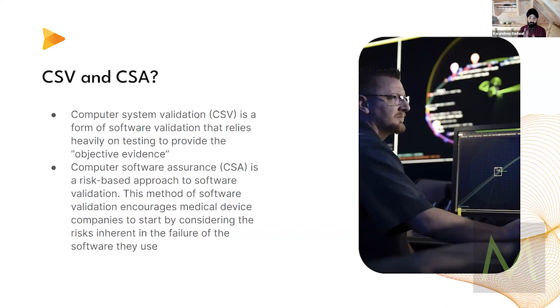I know the FDA is moving towards CSA, but for the purpose of today I'm going to be focusing on CSV. When it comes to CSA, there's a conversation we can have another time. The trick is kind of like the wording used in ISO 14971 and ISO 13485 — we take a risk-based approach. The higher risk things, yes, we need to double down on them. But things that are lower risk, maybe we can let them slide. Because if you just had to validate everything, you'd be spending hours validating and you would never release a medical device on the market. You do a risk assessment and see the level of validation required.